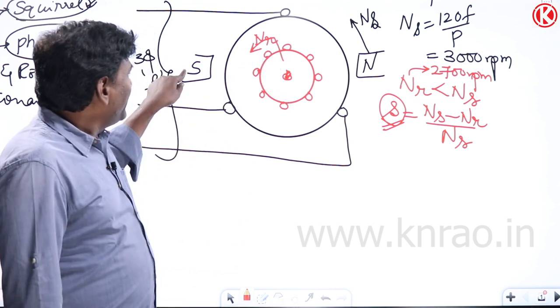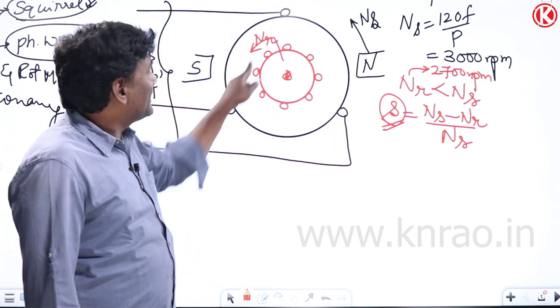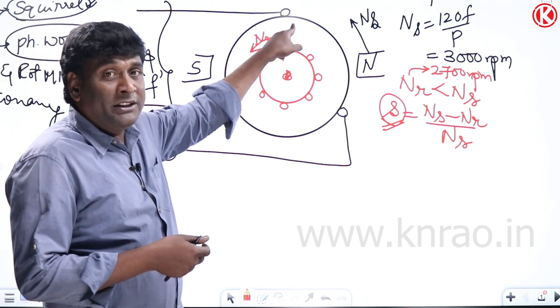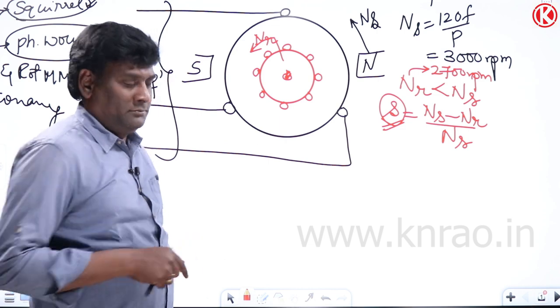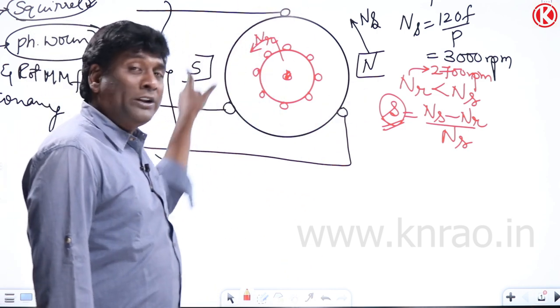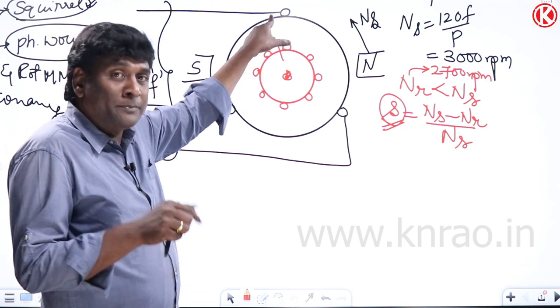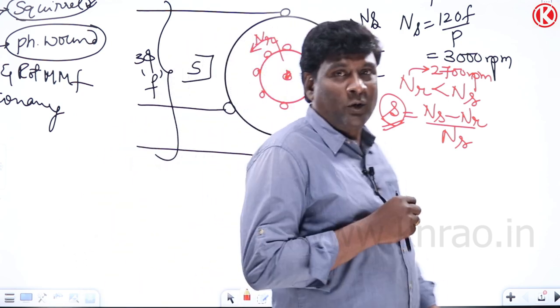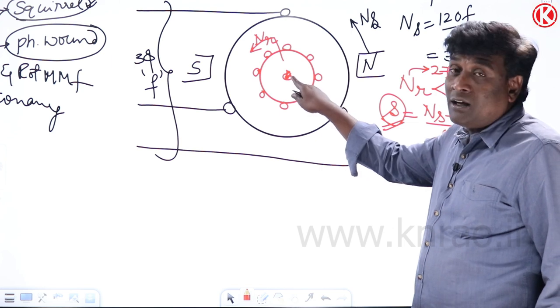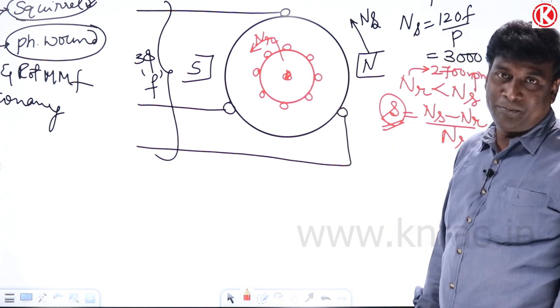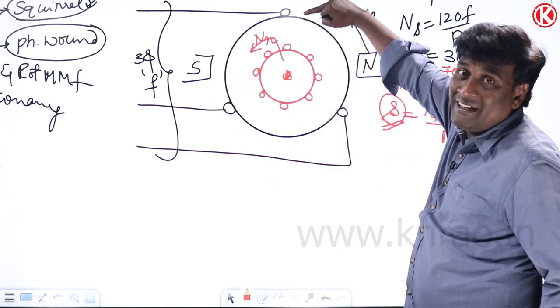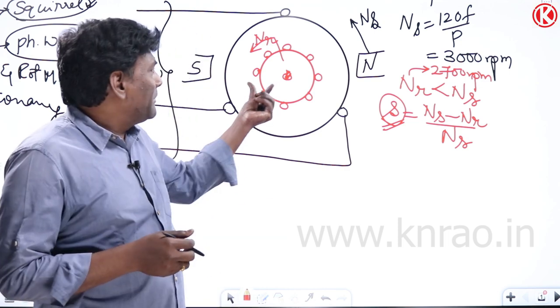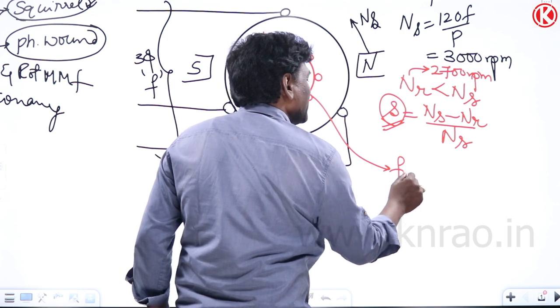When the rotor is stationary (0 RPM), stator MMF rotates at 3000 RPM relative to the rotor, so rotor frequency equals the stator frequency F1 (50 Hz) and slip = 1. When the rotor rotates at synchronous speed NS, the relative velocity is zero, so rotor frequency = 0 Hz and slip = 0. Therefore, rotor frequency = SF and slip varies from 0 to 1.